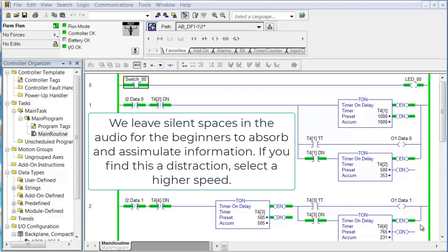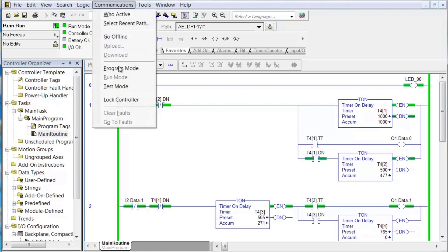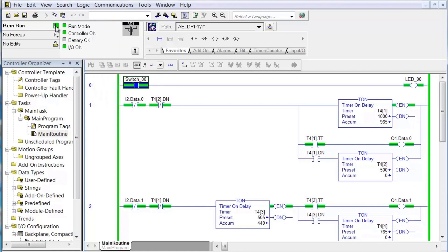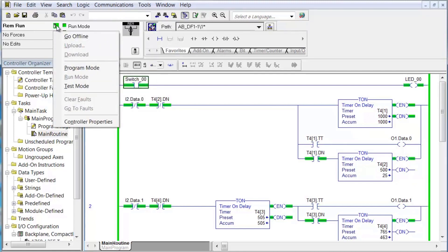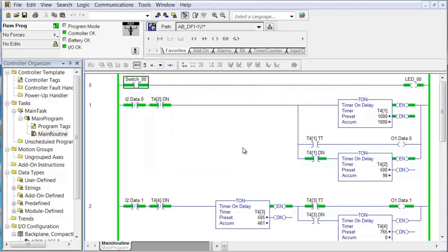First one is switching processor modes. If you look on the screen you'll see that we're in the remote run mode. If that were blue it would be program mode; if it were gray it would be offline. You can see we're running because you can see the logic executing. If I want to change modes I can do it from here — I can select different modes, but normally I suggest clicking over here on the current mode, picking the mode that you want, answering the default question, and now we're in the remote program mode.